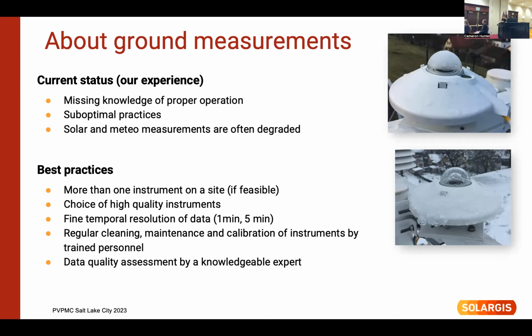So what we can recommend as best practices is that there should usually be more than one instrument on the site, so you can double check. Also, you should choose a high quality instrument. It is also good to have a fine temporal resolution, so it's better to have 1 minute or 5 minute data than hourly data.